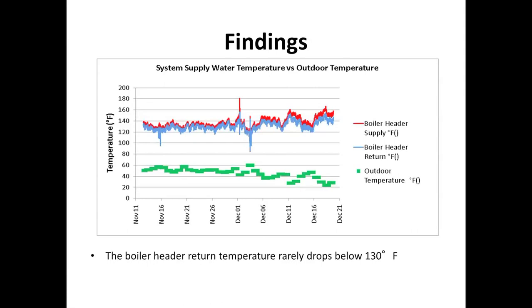So looking at this data that was collected, we saw that the supply temperature and return temperature of the boiler really weren't different from each other. With a condensing boiler, you really want return temperature coming back at less than 130 degrees. In this case, we didn't have a big delta T between the two temperatures. So the boilers really weren't condensing as they were supposed to, which indicated to us that we really need to make an improvement to reduce the return water temperature.